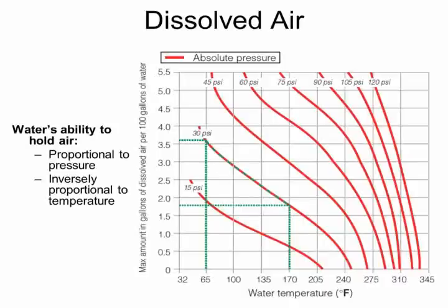So how do we use this, and how do we apply this to our designs? Well, let's say that we have a heating system. You have a boiler, you put it into the mechanical room, it's going to deliver heat to the first, second, third, and fourth floors up. You install the boiler, you design the system, and you have specified that at the boiler you want 30 psi of pressure, and that would be represented by this point here. Now this is 30 psi of absolute pressure, which means 15 psi gauge pressure.